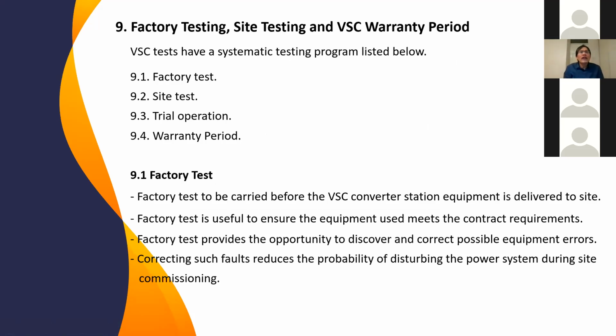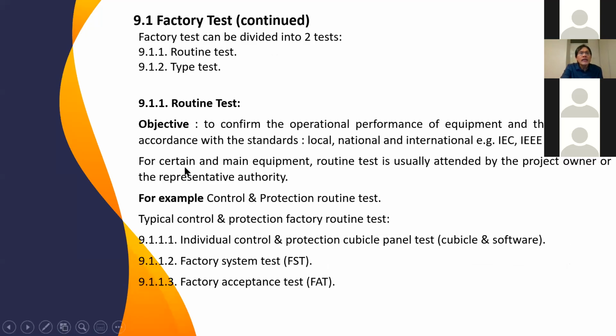So now we move to factory test. There are 4 types of tests: factory test, site test, trial operation, warranty period. Factory test is to be carried out before the VSC converter station equipment is delivered to site. Factory tests provide an opportunity to discover and correct possible equipment errors. For main equipment, sometimes factory tests will be witnessed by the customer. There are 2 types of factory tests, routine tests and type tests.